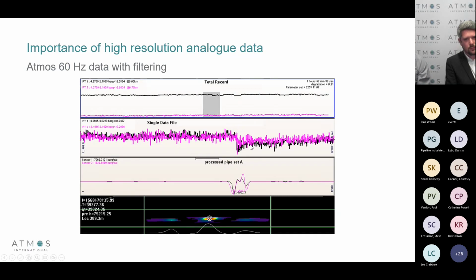Let's look a little bit deeper again. This is a screenshot from an engineering window that we use at Atmos. The top trend is pressure data on a similar scale to what you would expect to see in a control room. And what you might notice is that there's a very small change in pressure here, but unless you're actually looking at it all the time, you'll more than likely miss this at the sample rate of a SCADA system. At 60 hertz, you'll be able to see this very small change in pressure.